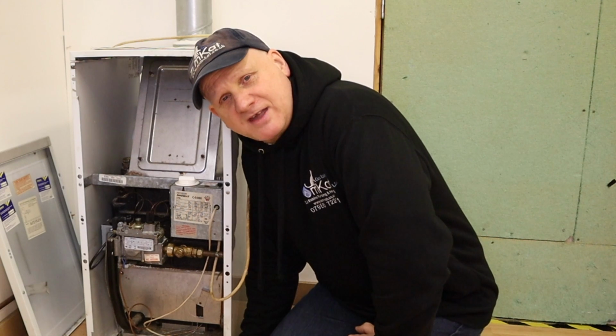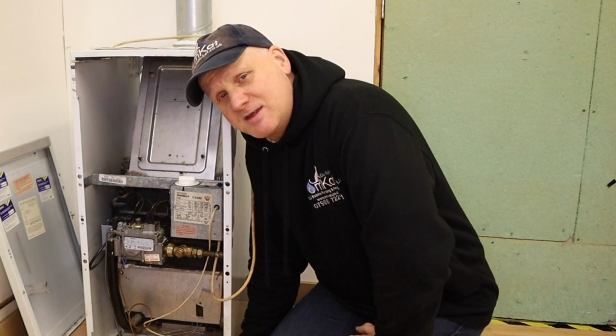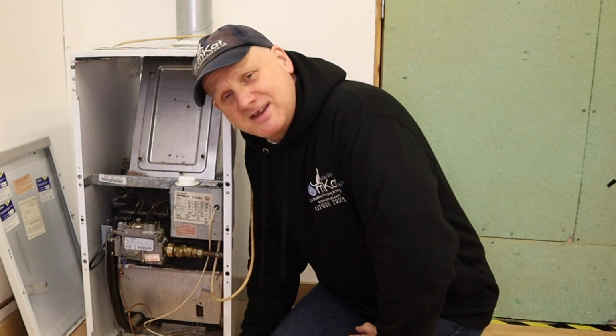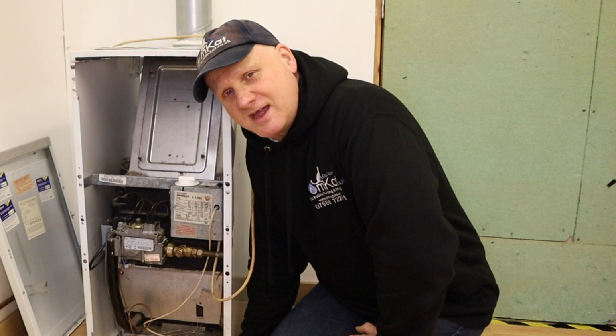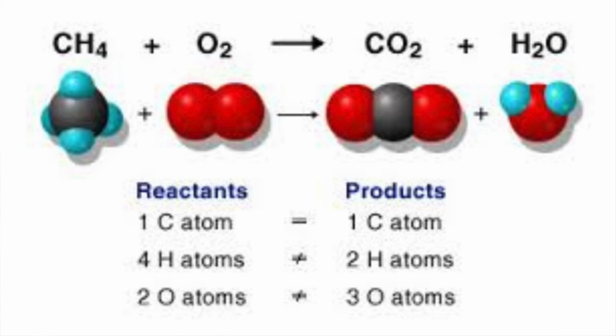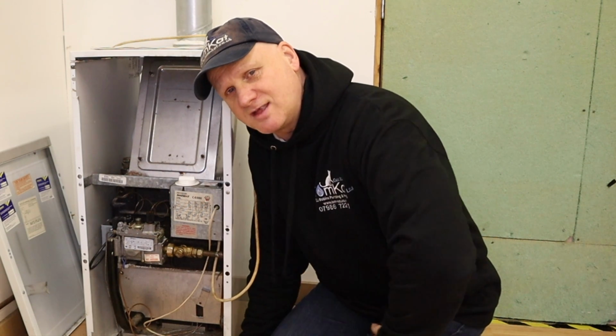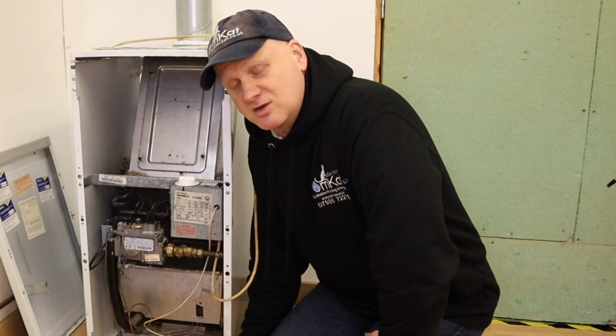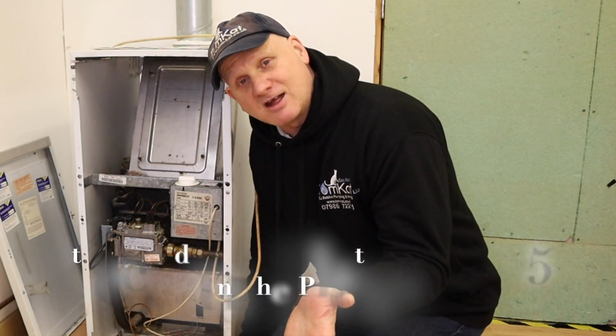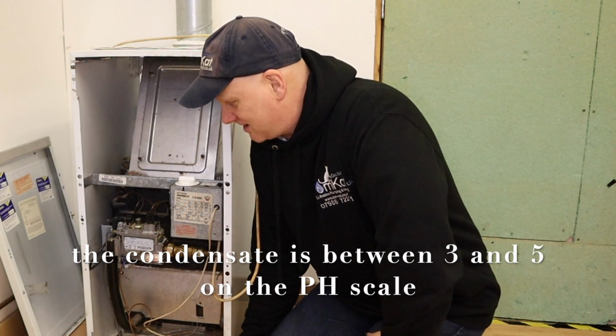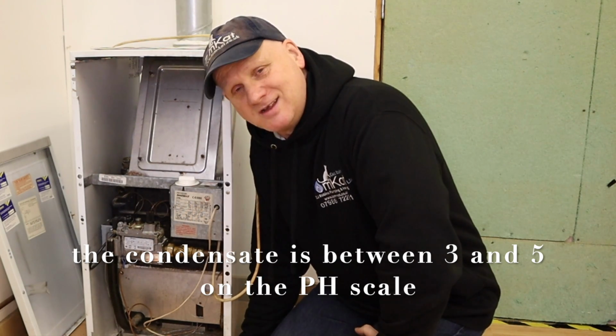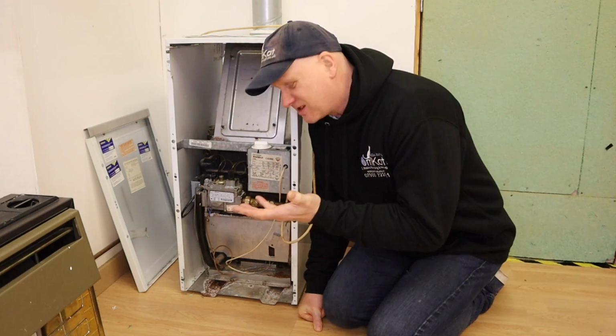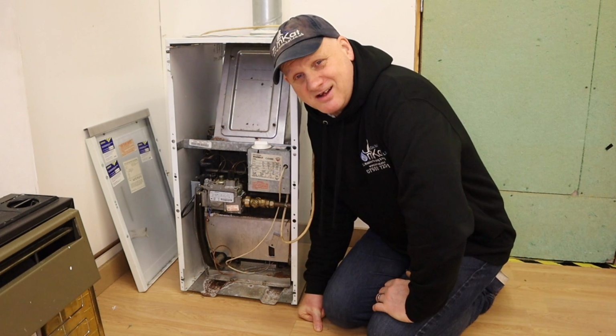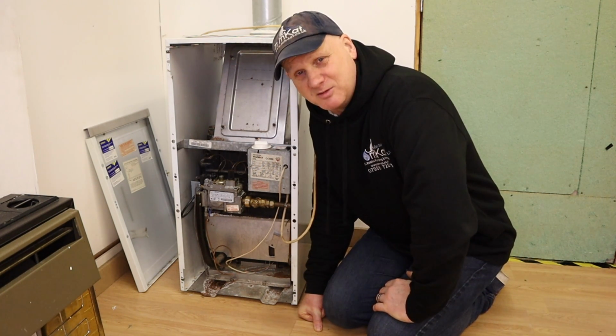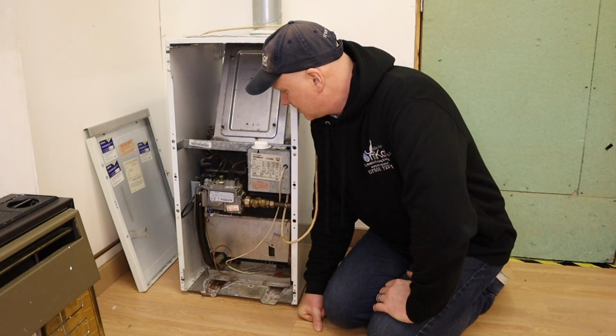Now, the reason why we don't have cast iron heat exchangers today is because of condensing boilers. And cast iron isn't very good for condensing, because when boilers condense, the water they produce, that's why they're called condensing boilers, because the byproducts of burning natural gas are carbon dioxide and water vapour. And what the boiler is doing is it reduces the flue temperature so much that those water vapours turn back into water and condense, and that's why we call them condensing boilers. But that water is very acidic, and cast iron heat exchangers don't like acidic water, so they would rot very easily. So because of all this, these cast iron heat exchangers don't meet all the energy saving requirements we need now for Part L of the building regs. So that's why manufacturers don't use cast iron heat exchangers.